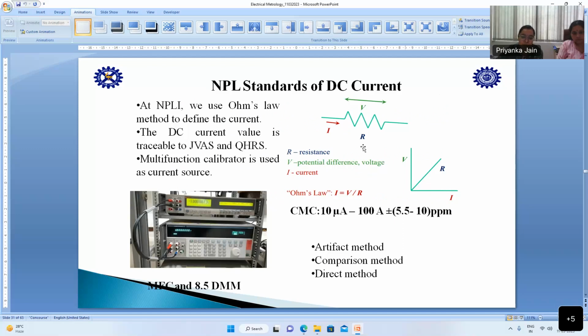So this is a normal methodology, that is Ohm's law, if you are applying it to a resistor. Another methodology is this. I have multiple resistances from 1 ohm to 100 teraohms. Using that resistance, I am able to generate variable current. For example, if I have a 1 teraohm resistance standard, I am capable of generating 1 picoamp to 100 picoamps using that range. So we have several ranges of resistance, so we can measure several ranges of current for lower level and higher level. The CMC presently available with us is 10 microamps to 100 amps using this multifunction calibrator.